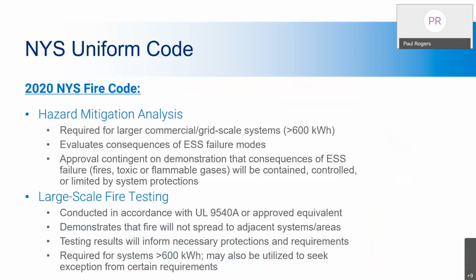So then back to the New York State Uniform Code, Chapter 12. One of the requirements that may be needed if you're putting some installations in is a hazard mitigation analysis. That is a failure modes and effects analysis, an FMEA. They just want to know, if this thing were to fail, what mitigation is in place, and what happens if this component or something else were to fail. That is required on some installations that are large scale. And there are other requirements in the code that mention where this HMA, which will spark an FMEA, is needed. As I mentioned before, it also evaluates the consequences of the ESS failures and what protections are in place. So just a word for those people or any AHJs out there: there are a lot of layers of protection in here that need to fail in order to have a failure.